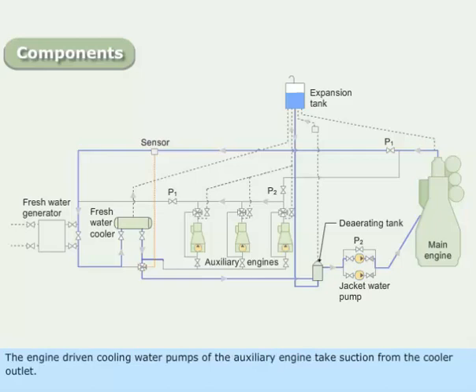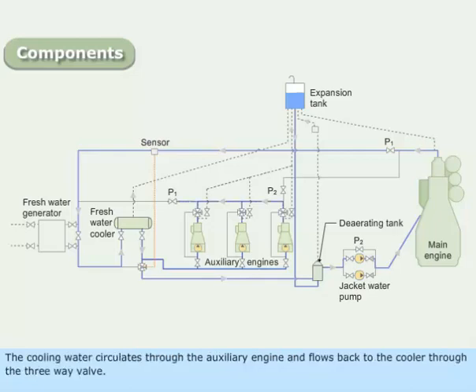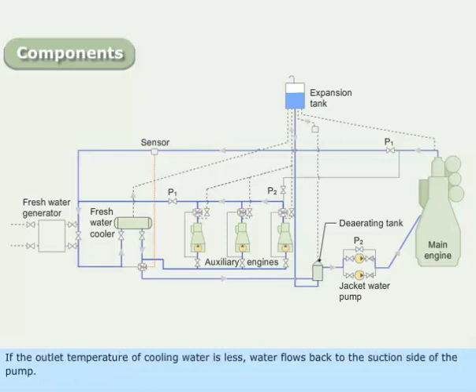The engine-driven cooling water pumps of the auxiliary engine take suction from the cooler outlet. The cooling water circulates through the auxiliary engine and flows back to the cooler through the three-way valve. If the outlet temperature of the cooling water is less, water flows back to the suction side of the pump.